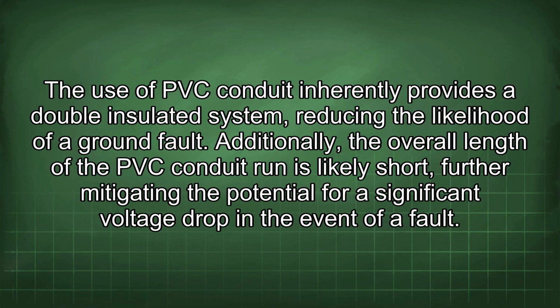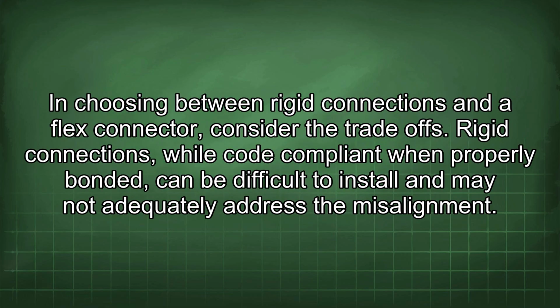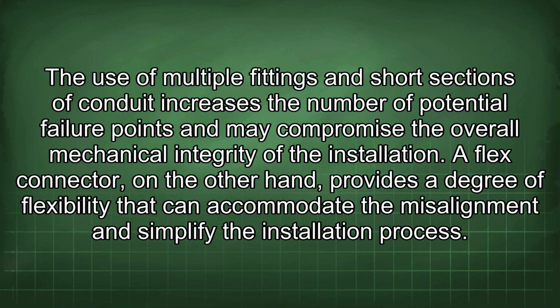The use of PVC conduit inherently provides a double insulated system, reducing the likelihood of a ground fault. Additionally, the overall length of the PVC conduit run is likely short, further mitigating the potential for a significant voltage drop in the event of a fault. In choosing between rigid connections and a flex connector, consider the trade-offs. Rigid connections, while code-compliant when properly bonded, can be difficult to install and may not adequately address the misalignment. The use of multiple fittings and short sections of conduit increases the number of potential failure points and may compromise the overall mechanical integrity of the installation.